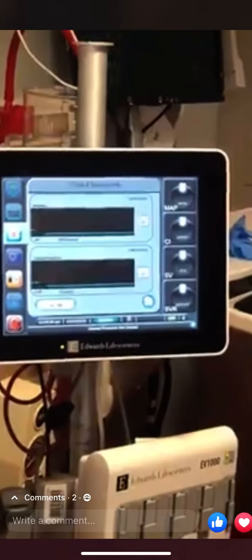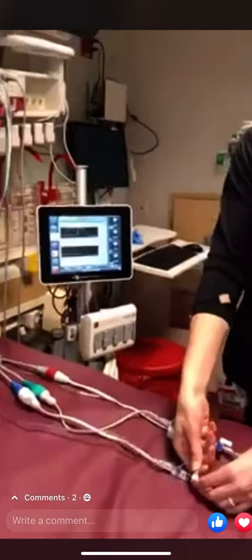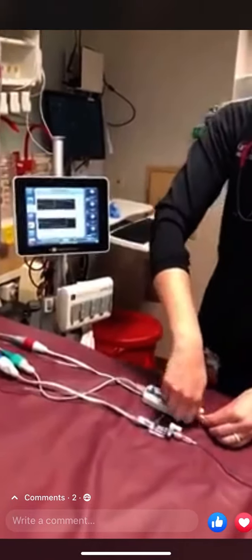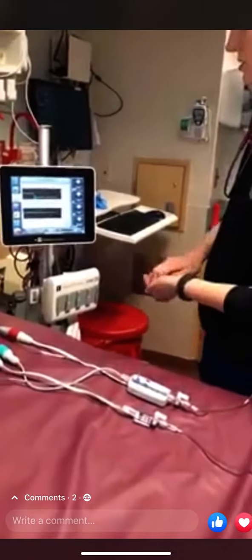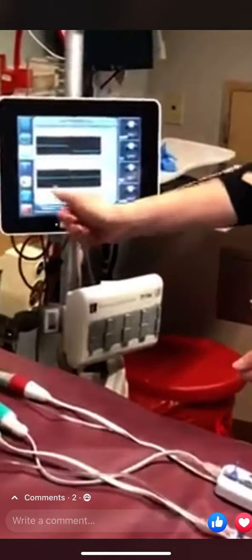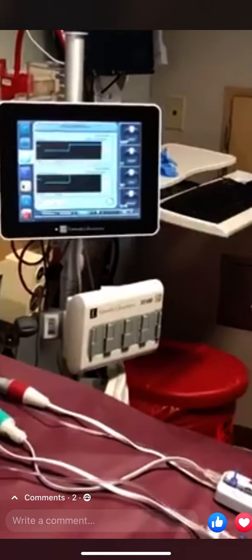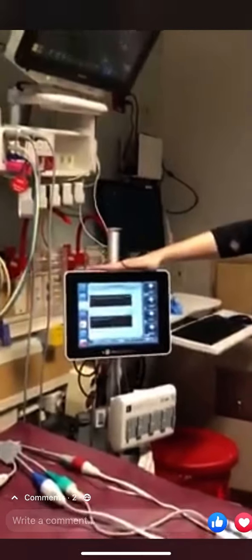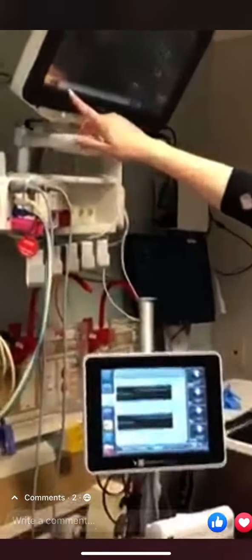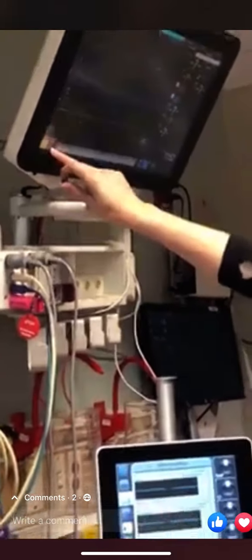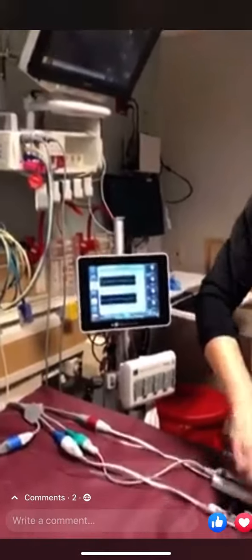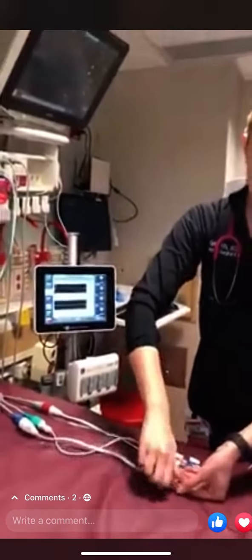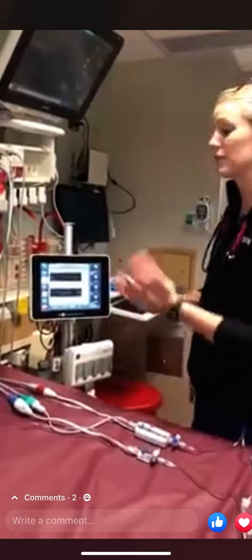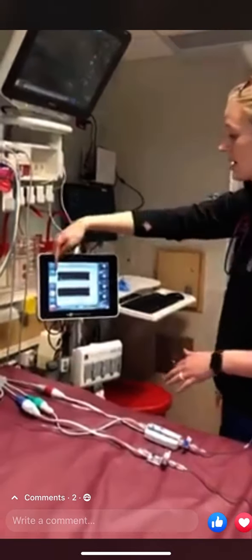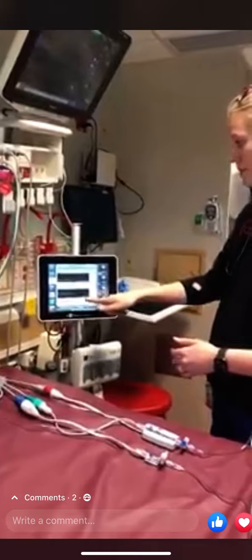So all you have to do at this point is 0 both of your transducers. So you want your patient flat because we're doing a CVP. You will level both your transducers at the phlebostatic axis and hit 0 all. Obviously, ours is not going to 0 because we don't have these connected to a patient. When you 0 these, you will also go ahead and 0 them on your monitor as well. Once you hear the 2 beeps, you can set them back up. Plug everything back in. And then you should, if you have these both hooked up to a real patient, see an arterial waveform and a CVP waveform.